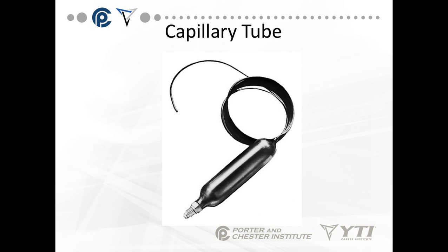This is an example of a cap tube. You'll see the coil in this area of the cap tube, and this is actually attached directly to a filter dryer, so this side is coming out of your liquid line. We go through our cap tube and this side connects into the tube right before the evaporator and actually sprays into the evaporator.